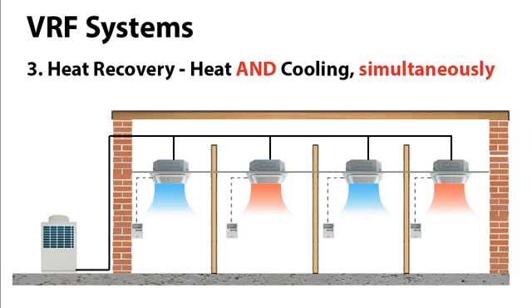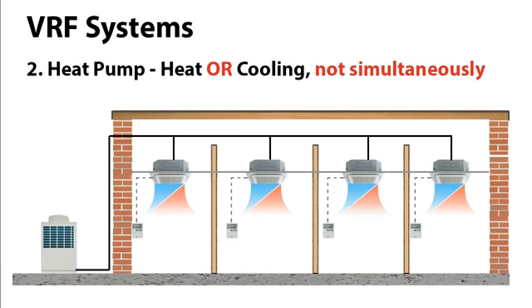And then the third option we've got is the heat recovery VRF system, and this is much more advanced and much more complex, and we'll see these in later videos. But in this scenario all the units within the building can all be designated as separate zones, and they can be heated and cooled simultaneously. Now in all these cases, each zone, as you can see here, has its own controller, and that can control the thermal temperature of its individual zone without affecting the other rooms. So this unit can be switched off, and this one can be switched off, and this could be on, and this one could be off, and the system will continue to work without being affected by the other units.